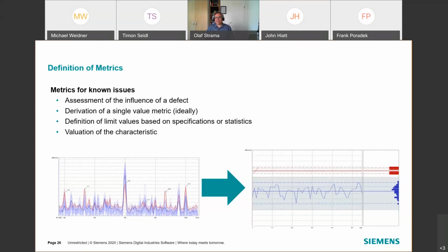We sometimes have an influence if there's a structure on the surface, that the structure does a kind of beam forming of the laser beam. The laser beam is not reflected back as a kind of cylinder or cone, but as a very small shape, and then we have to take care about setting up the perpendicular position of the laser.